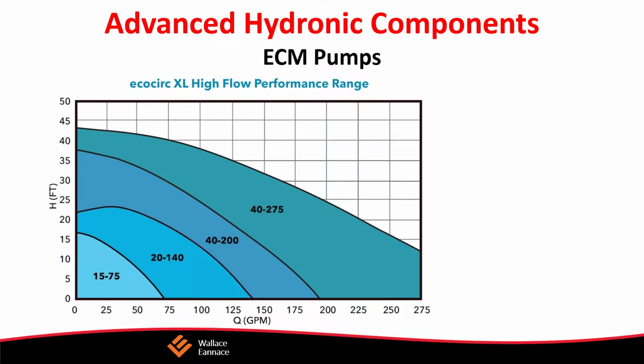So if I have 100,000 BTUs and I want 10,000 BTUs out of a 100,000 BTU boiler, it'll be 1/10. In that case, there's a 0 to 10 volt output. That output would actually put out 1 volt. If it was putting out, say, 50,000 BTUs, it will put out 5 volts. And that 0 to 10 volt input can be used to drive this pump.